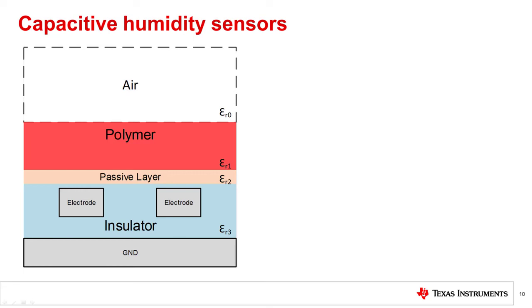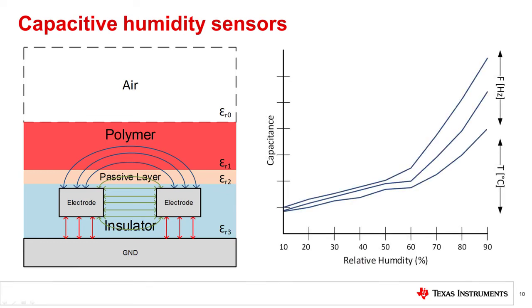A more realistic view of how these kinds of capacitive RH sensors may be implemented is given here. In this design style, two electrodes are enclosed within an insulative dielectric, in this case above a common ground plane. The polymer is above these electrodes separated by an additional passive layer. When active, there is an electric field and an associated capacitance that exists between these two electrodes, shown in green, and between each electrode and ground, shown in red. These lines show the portion of capacitance which is not dependent on RH, as they do not extend through the sensing polymer. It is the fringe field lines which actually cross through the sensing polymer that are affected by the change in electrical permittivity of the polymer over RH. This kind of topology has a more complicated relationship than our ideal parallel plate capacitor example, but it is easier to manufacture for integrated circuits.